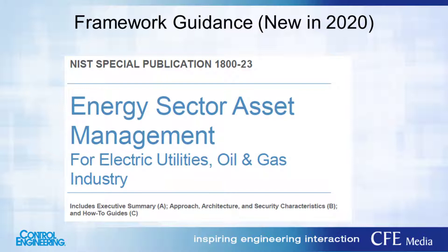Earlier this year, NIST produced a new special publication, 1800-23, which is really helpful because it puts a cybersecurity program in the context of asset management — a model many operating companies already use to manage physical and mechanical integrity. This document frames cybersecurity in that context: develop an asset inventory of what needs to be protected, assess the risks, and identify areas to invest in for protection. It's new this year and fits with terminology that many operating companies already use.